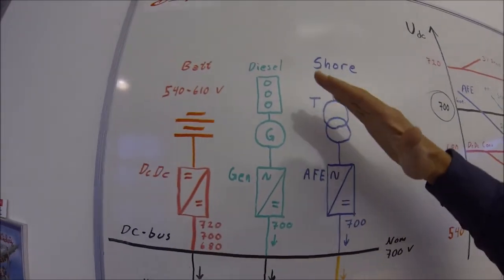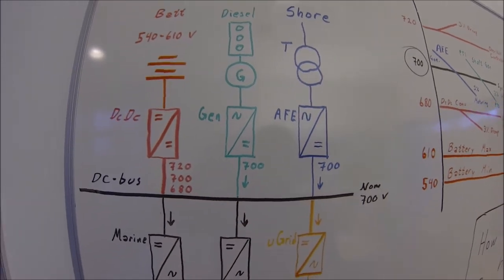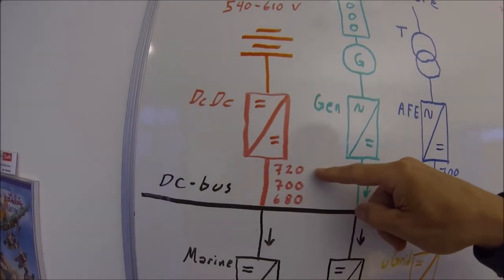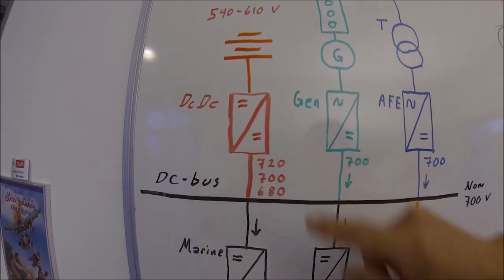In the other direction, let's say you are feeding more energy into the DC bus than your consumers can absorb. Then the voltage will increase until 720 volt, which is my over-voltage controller level.